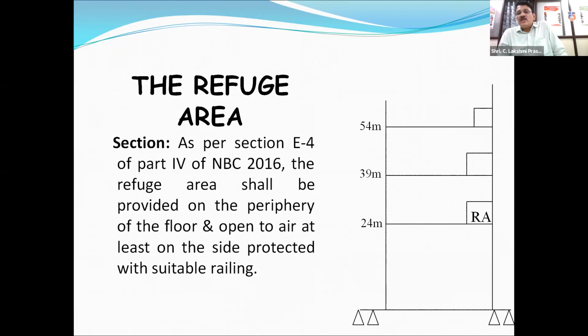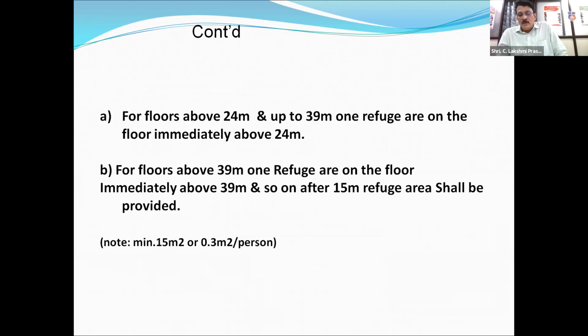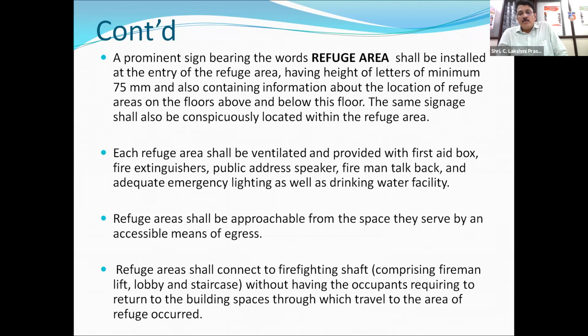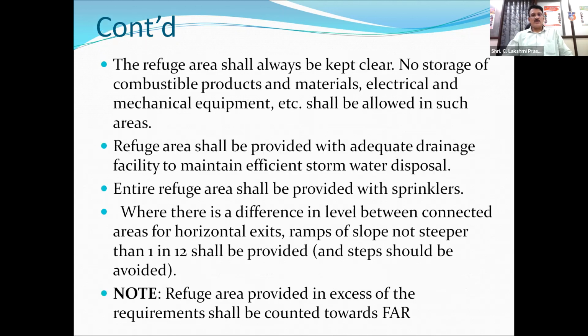This should be protected from fire with a 2-hour fire resistance enclosure, a fire door and talk back facility. And one side should be open to the atmosphere with an openable railing, because in case the fire department comes with its hydraulic platform, they should be able to approach that area. If it is entirely closed, then people cannot be rescued. So that is the logic. Refuge area is very, very important for all buildings. For residential buildings, it should be provided after every 60 meters, for every 30 meters. For commercial buildings, from 24 meters onwards, it has to be provided for every 15 meters, to accommodate the occupants of 2 floors.